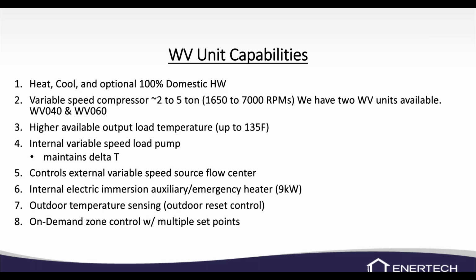There's higher available load temperatures on this unit. We can get up to about 135 degrees. Obviously, the lower water temperature we can use, the better, because it's more efficient, but we can go up to the higher water temperatures. We use an internal variable speed load pump that maintains your temperature difference, or your delta T, across the load circuit. So it'll throttle and base its speed on the delta T. It basically tries to maintain a 5-degree delta T across the load in and the load out.